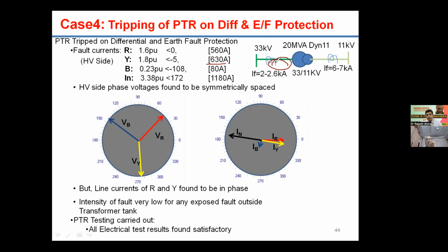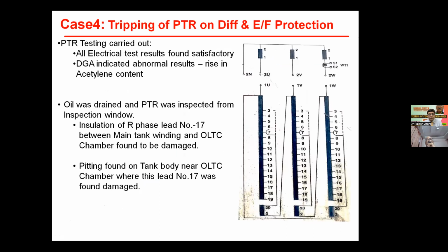So electrical tests of this transformer were carried out, and all electrical test results were found satisfactory, be it GST, tan delta values, WRM, short circuit, everything was fine. However, when we conducted the DGA of this transformer and compared with last year's values, there was a significant rise in acetylene content. So this acetylene formation indicated that some internal arcing is there in the transformer.